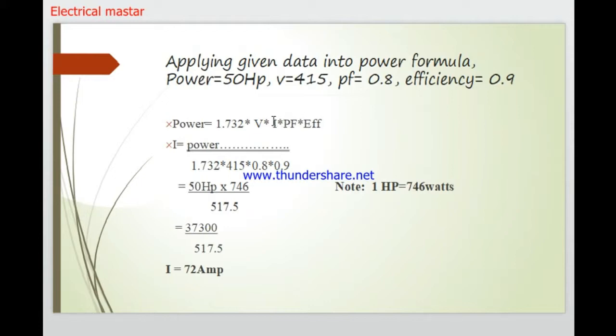Now, let's solve for current I. Rearranging the formula: I = Power ÷ (1.732 × 415 × Power Factor 0.8 × Efficiency 0.9). We insert the value: 50 HP × 746 = 37,300 W, since 1 HP equals 746 W. So 50 HP into 746 gives us the numerator, which is then divided by the denominator values to give the full load current.